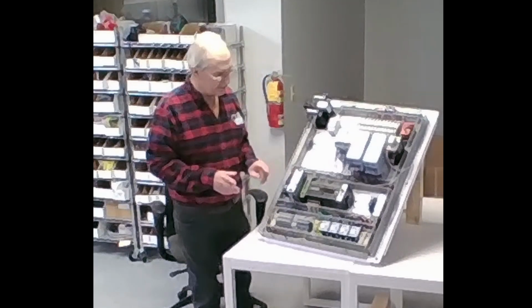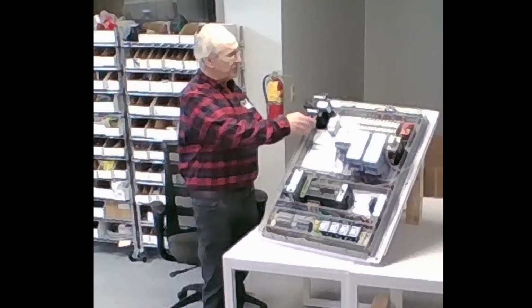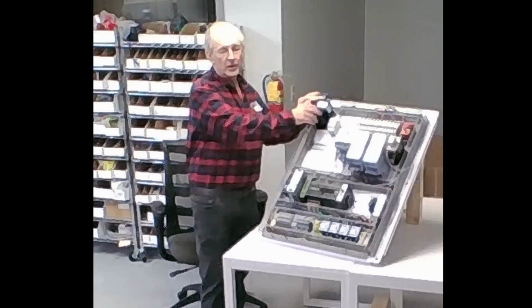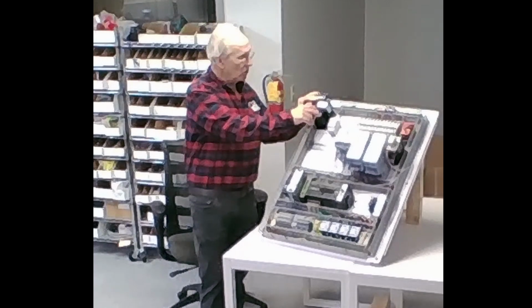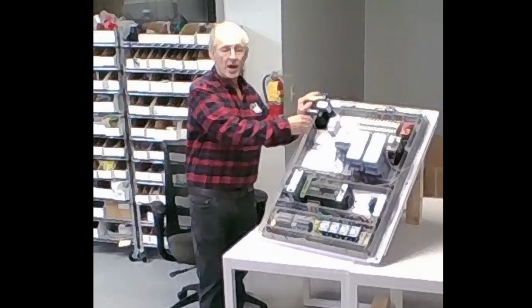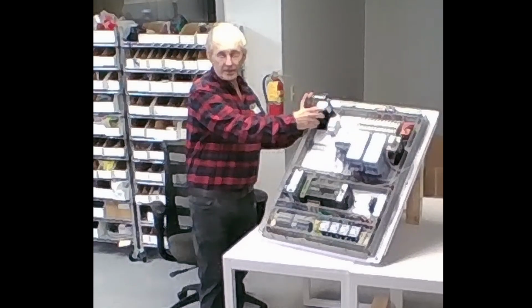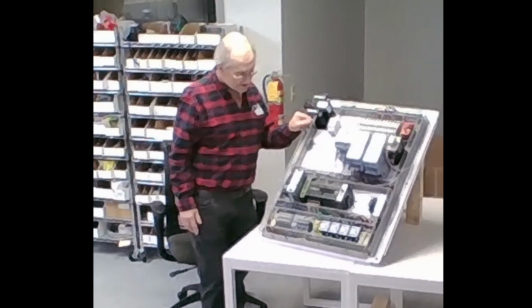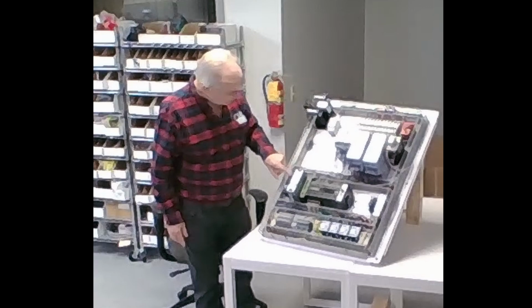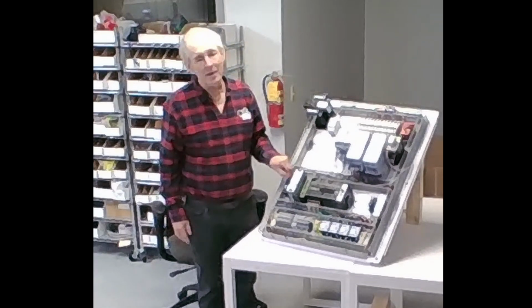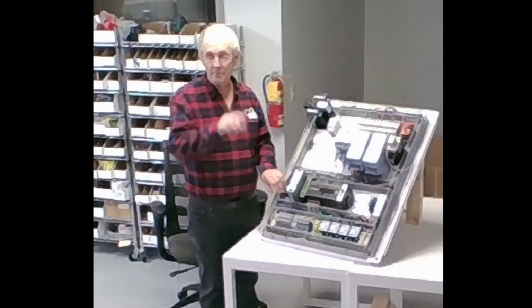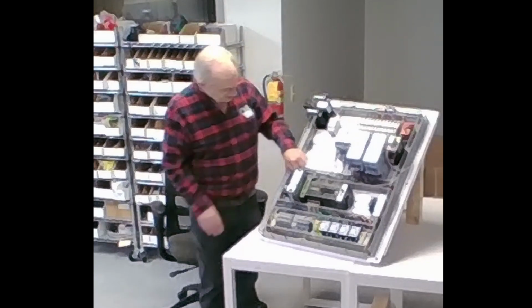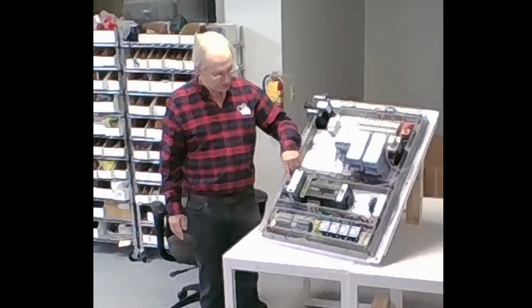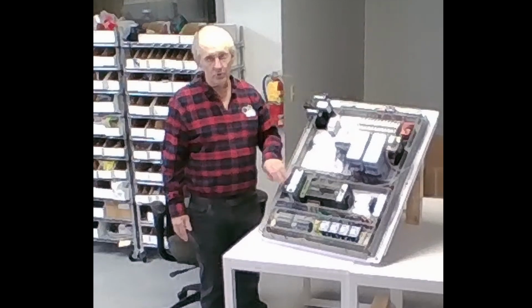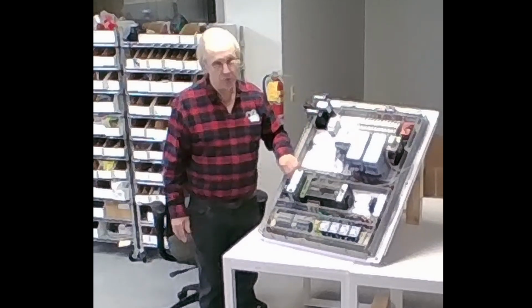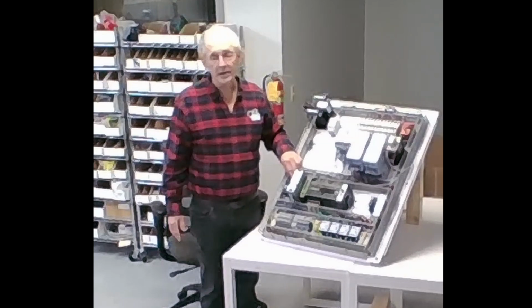There's always a master fuse. In other words, you come off this transformer and you want to protect the transformer from overload. So you use a fuse in the hot wire that is sized to handle the load the transformer can safely handle. We come out of there and down through a fuse, in the top of that fuse and out the bottom, because it's always fed top to bottom. Then we loop around and come up, and we have jumpers going across to 4 more fuses. The first fuse protects the transformer, and the rest of the fuses protect the loads connected to it.